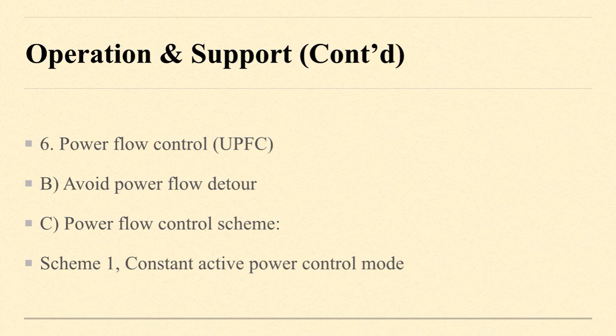Next is avoid power flow detour. The third is power flow control scheme. Scheme 1, constant active power control mode. The advantage is it can reduce the frequent adjustment of valves to the transmission power and improve the operation reliability. But according to the wind power prediction, the DC power transmission curve needs to be constantly revised, so it makes the operation management much more complex.